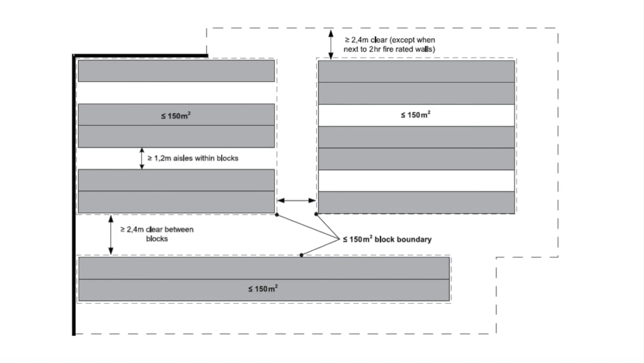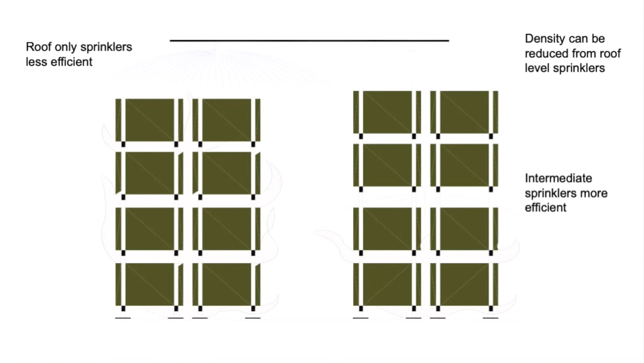palletised racking. There are 2 ways of protecting palletised racking. You can protect it from the roof only. From the roof only, on the left-hand side, you can see where the fire goes. There's space around it to grow. So you can't store too high, otherwise you get a high density of water at the roof. The other option is to put sprinklers inside the racks. It's called in-rack sprinklers. When you've got in-rack sprinklers, you don't need as much density in the roof because the fire's also being contained within the racks itself. For instance, you might need 35.5 millimetres a minute on the left-hand side, and on the right-hand side, you might only need, all in all, about 15. It's a lot less water on the floor, a lot less water damage, a lot smaller diameter tank, pumps, pipework, etc.